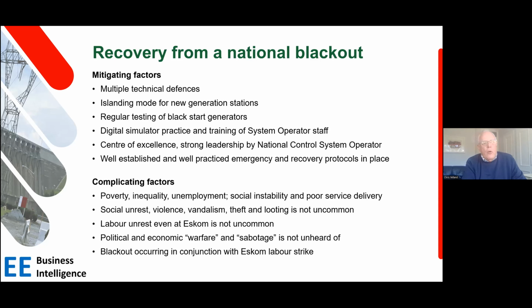We also have what's known as the islanding mode for new generation. Some of the new generating power stations at Eskom have an islanding mode. These are coal-fired power stations, and instead of shutting down completely, they operate the power station in islanding mode at a very low load, with the boilers still operating, still taking in some coal. If you switch off a coal-fired power station, it starts to cool down and takes a long time to restart.